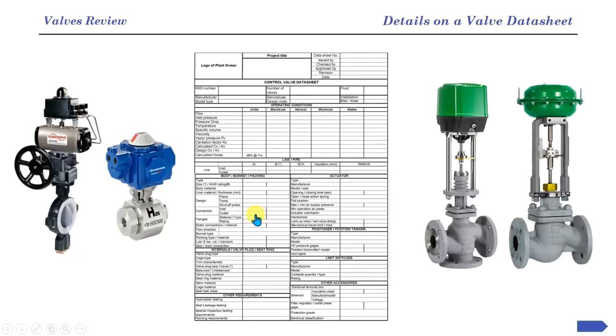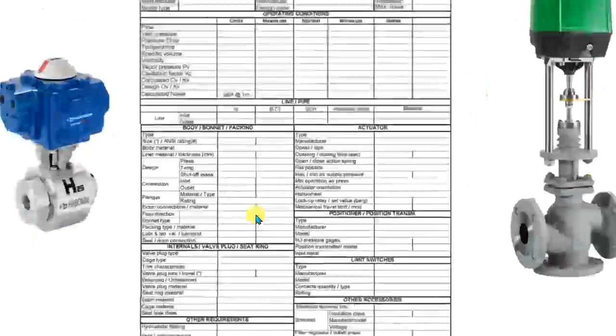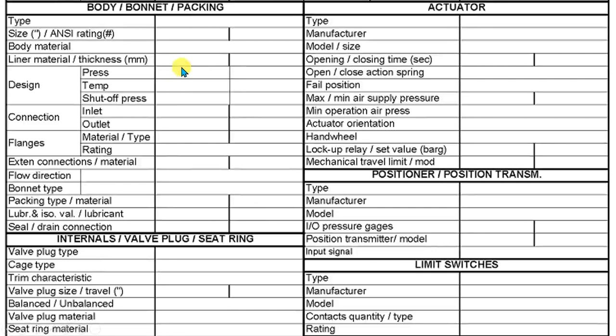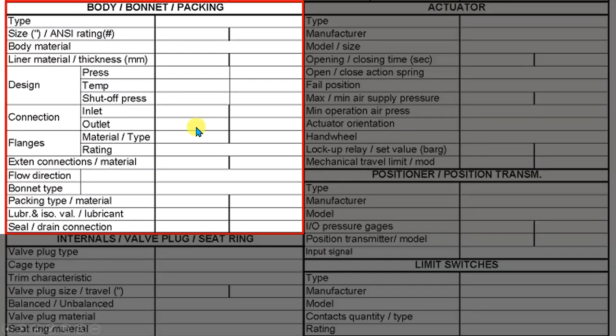Now let's jump into the parts that are more related to the valve itself. On the right hand side, you can see all the data related to the valve parts, starting from body and then bonnet, sealing, as well as internals called trim or wetted parts. Valve type can vary from linear globe valves or diaphragm valves, to rotary plug, ball, and butterfly valves. Then we have size and pressure class rating, mentioned as NPS in inches and class according to ASME B16.34 in the American context.